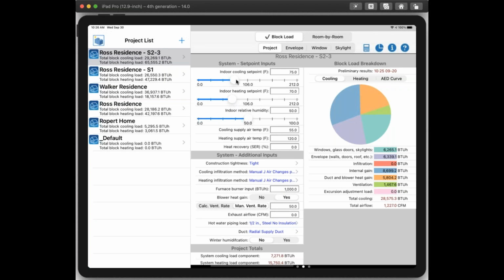So here we have set points. I can change my set point by sliding the slider control. And as you can see, when I change my cooling set point, it affects my cooling load. And as I change my heating set point, it changes my heating load. I can enter my indoor relative humidity. I can also enter my coil temperature in terms of the air coming off the cooling coil and then the air coming off the heating coil. Now this cooling coil temperature will affect my airflow because the airflow is calculated based upon not only the total cooling load, but also the difference in temperature between your set point and your coil temperature.